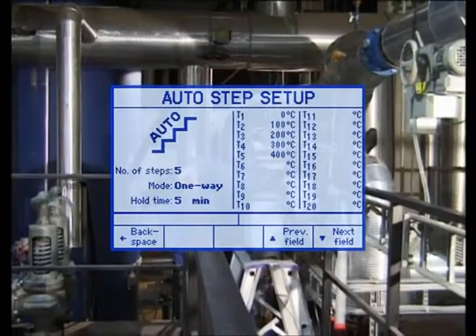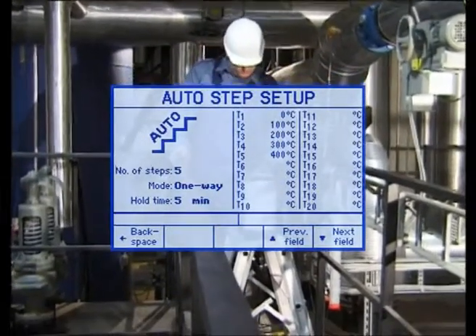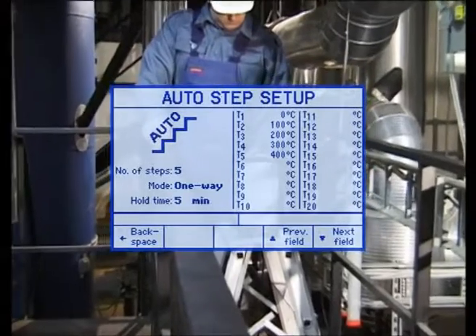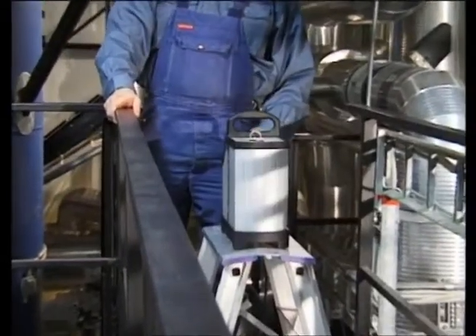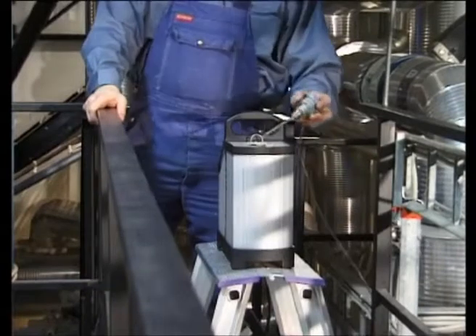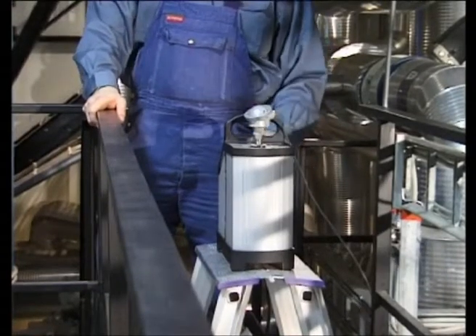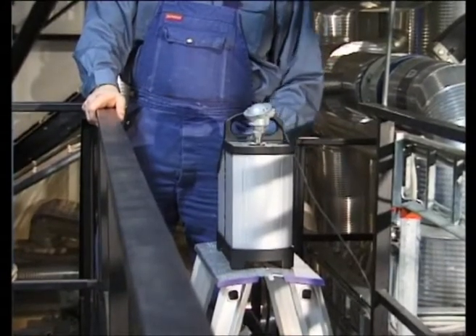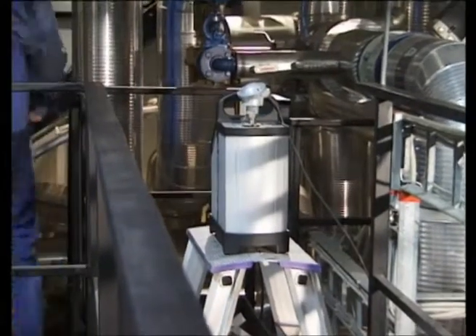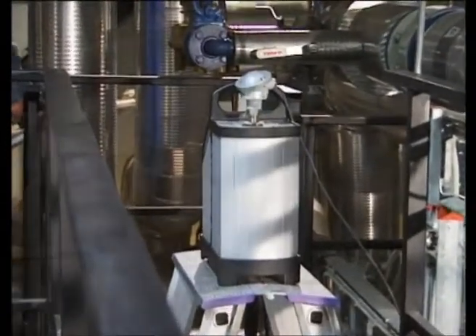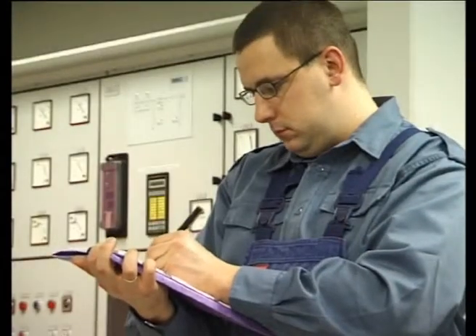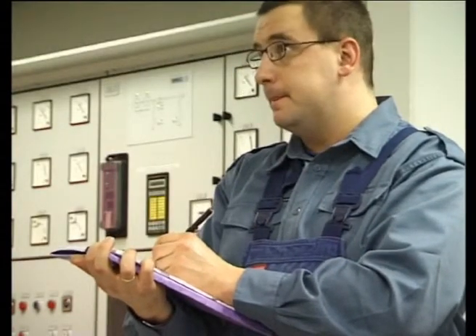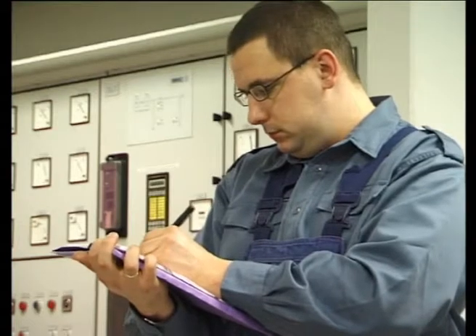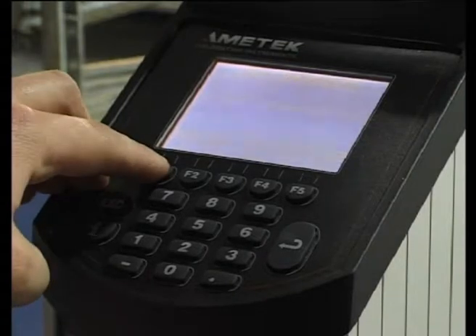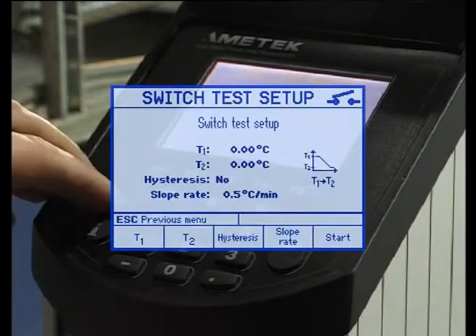Using the auto step function, the calibrator is able to change between a list of user-defined temperatures automatically. You define the temperature and the stability time required for each step. The calibrator is placed at the process line, thus allowing you to be at a distance, for example, in the control room, recording the values for the relevant sensor. Upon return to the calibrator, you can key in the results. Using the automatic thermostat test, the calibrator is able to determine the open, close, and hysteresis temperatures.